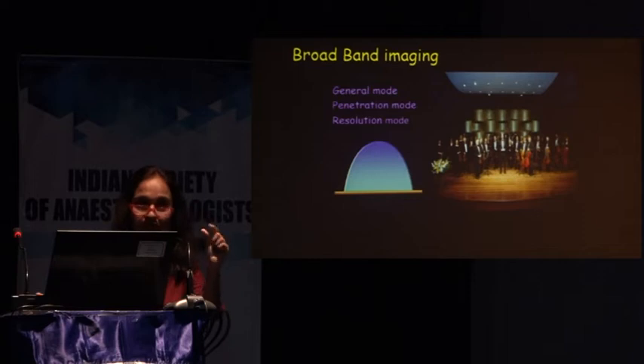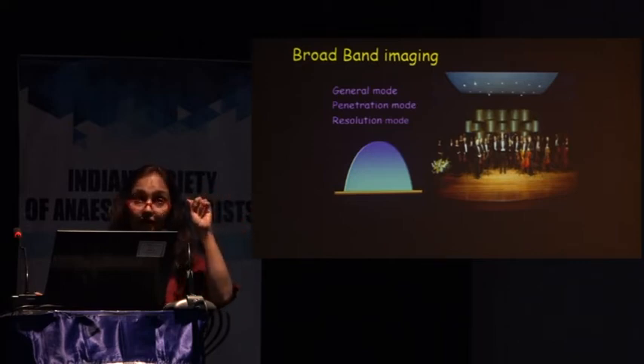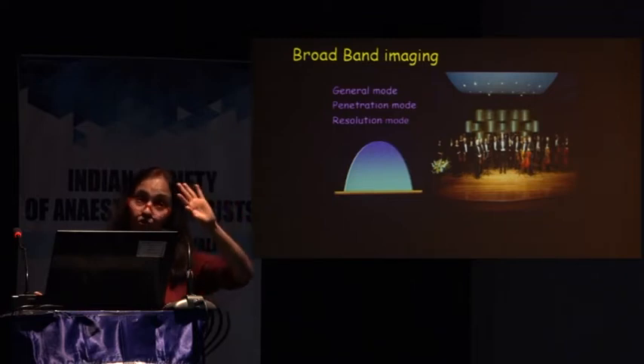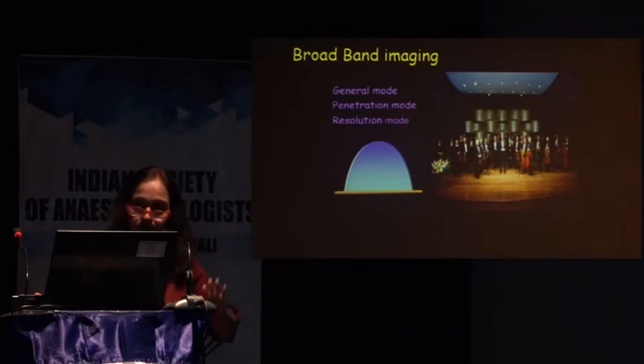Penetration shall be used in a given span of 8 to say 13. When we use penetration in this particular probe, we are asking the probe to give us the ultrasound waves of lower frequencies. Maybe 8 to 10, if that helps you understand. Okay? Resolution, I am selectively asking the ultrasound probe to give us higher resolution ultrasound, higher waves, maybe say from 12 to 13. Okay? So in a 10-year-old child, an IJV cannulation or an axilla, go to resolution mode of a given linear transducer.